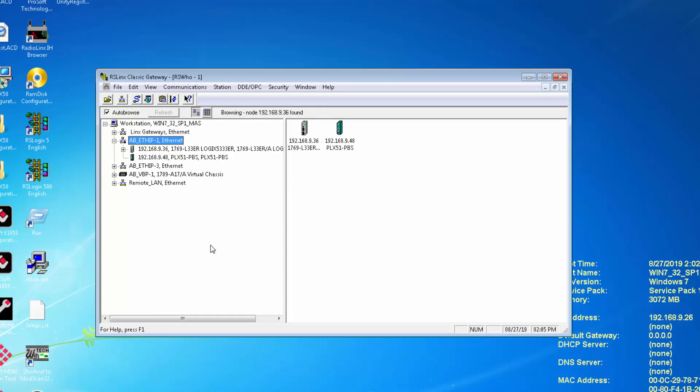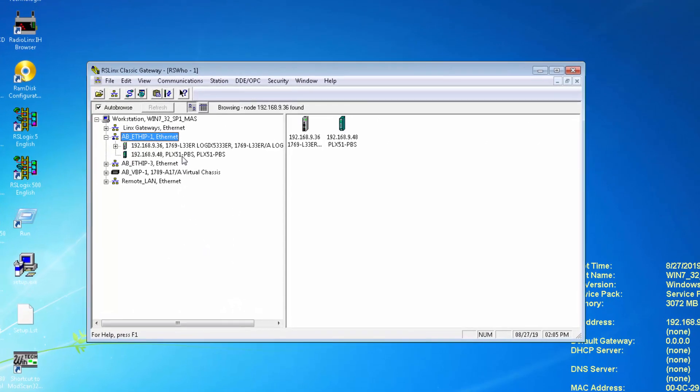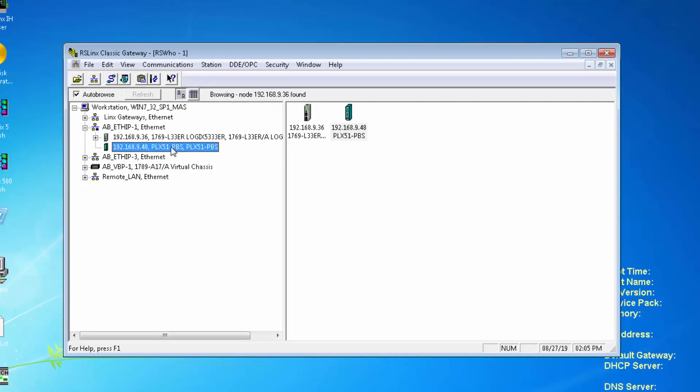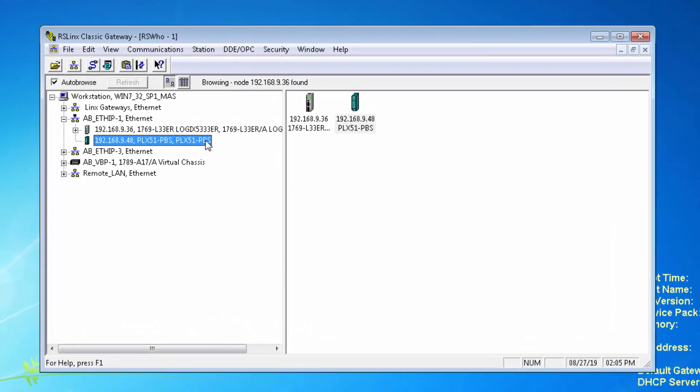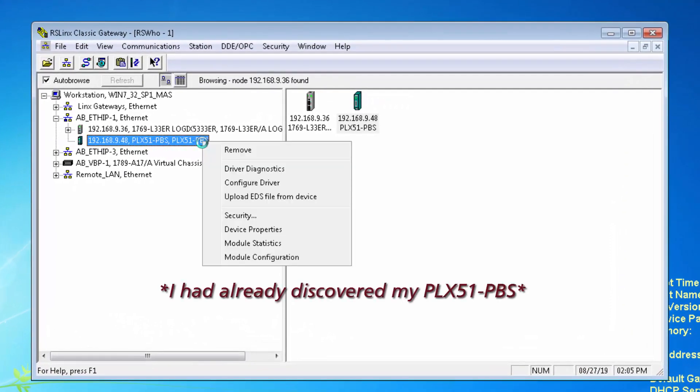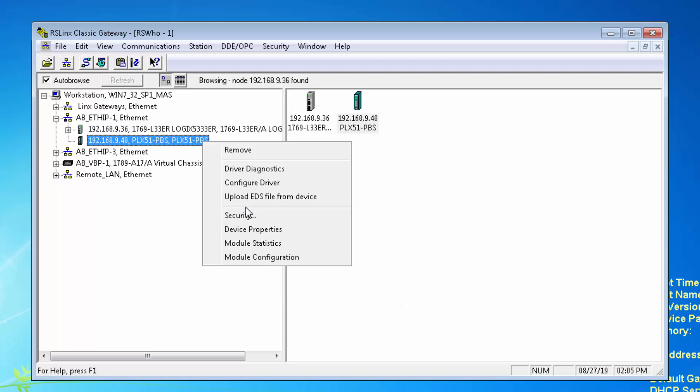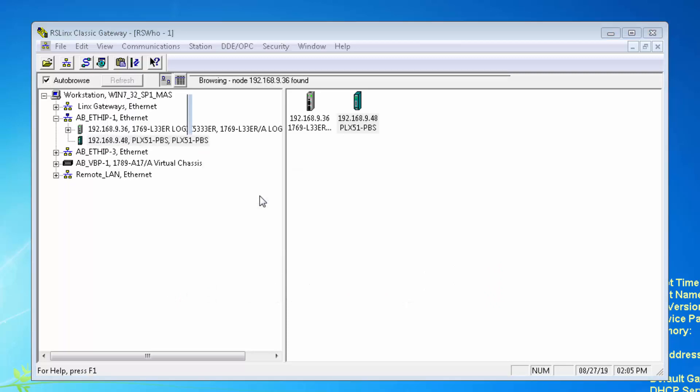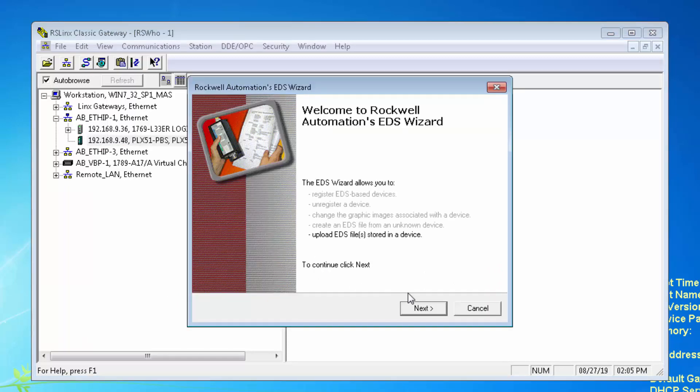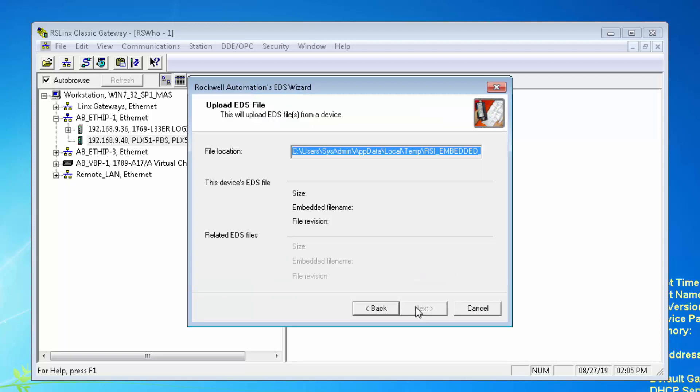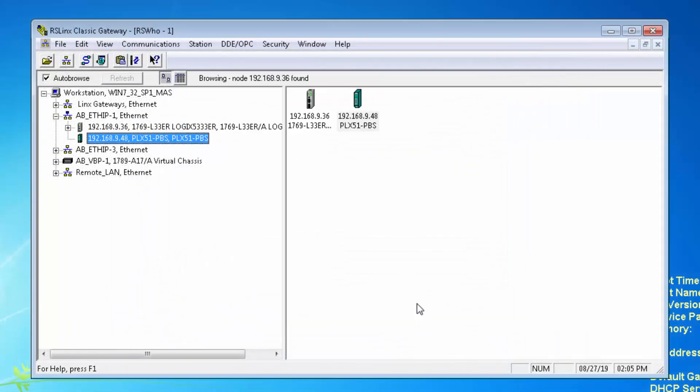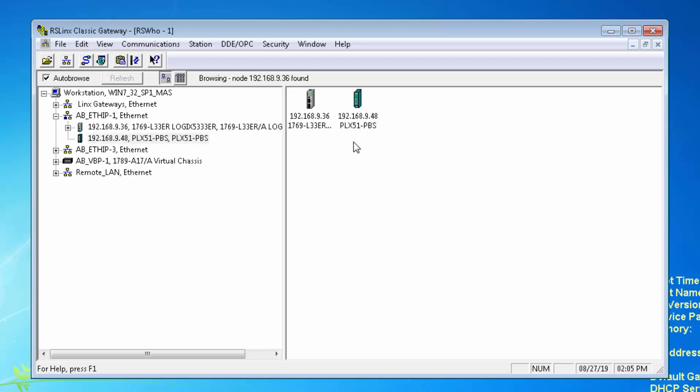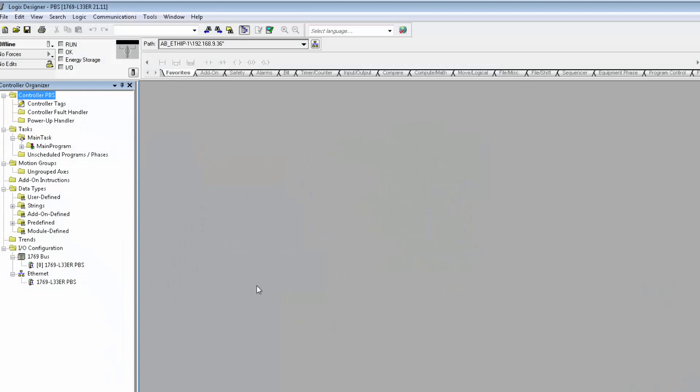The EDS file for the PLX51 is embedded in the module. So we'll open up RSLinx Classic, locate the unknown device on the network with the IP address that we assigned to the PLX51 PBS, right-clicking on it and selecting Upload EDS from Device. Let's keep clicking Next through all the prompts. And when it's done, we should see that the PBS is now recognized inside RSLinx. It's got its own little icon. And this gives us an AOP that will make the EIP side of the gateway recognizable to the Logix program.